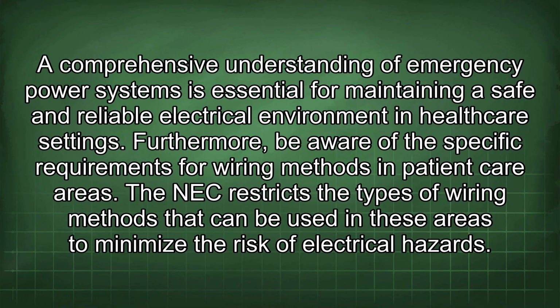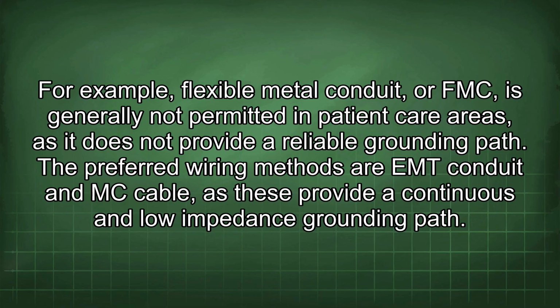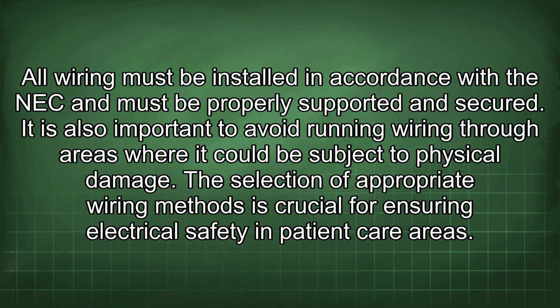The NEC restricts the types of wiring methods that can be used in these areas to minimize the risk of electrical hazards. For example, flexible metal conduit, or FMC, is generally not permitted in patient care areas, as it does not provide a reliable grounding path. The preferred wiring methods are EMT conduit and MC cable, as these provide a continuous and low-impedance grounding path. All wiring must be installed in accordance with the NEC and must be properly supported and secured. It is also important to avoid running wiring through areas where it could be subject to physical damage. The selection of appropriate wiring methods is crucial for ensuring electrical safety in patient care areas.